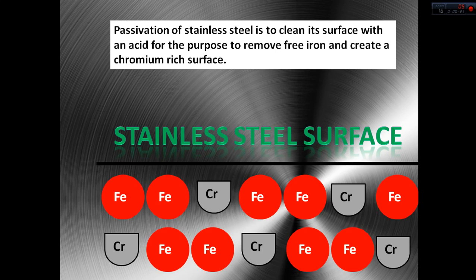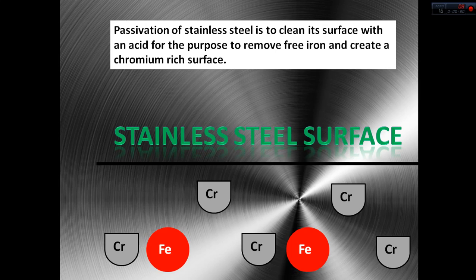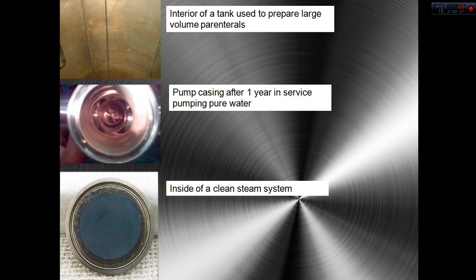Passivation means to clean the surface of stainless steel using an acid. When we clean it with an acid, we will remove the iron from that surface, and then the surface will become more rich in chromium and more corrosion resistant. There are many substances in the pharmaceutical industry that can corrode stainless steels.